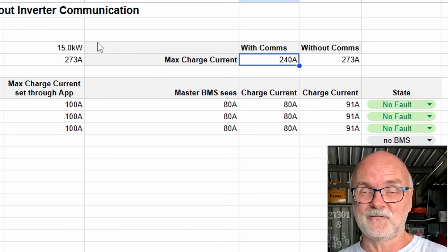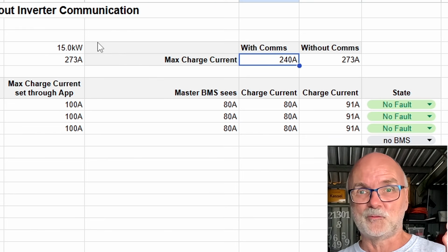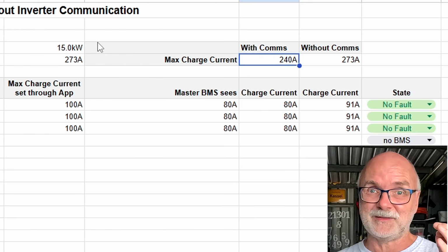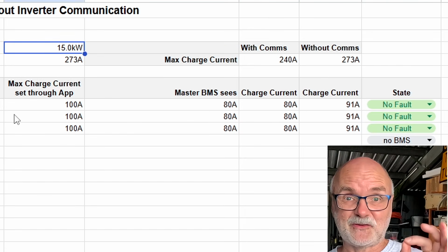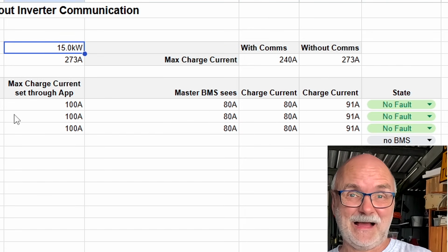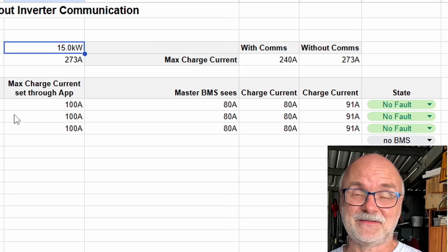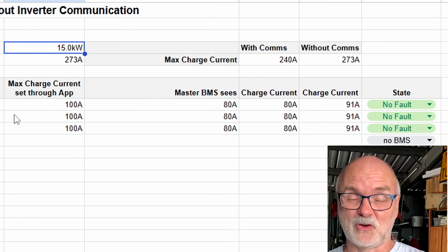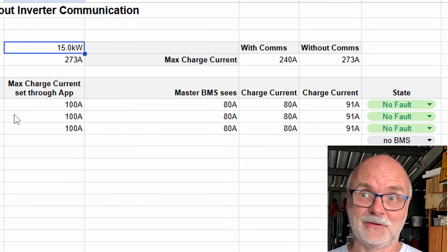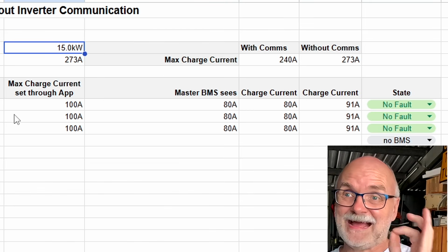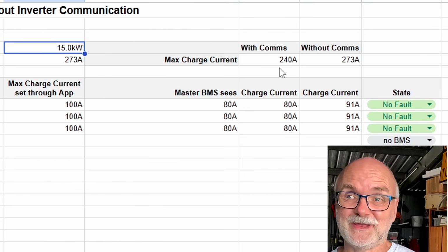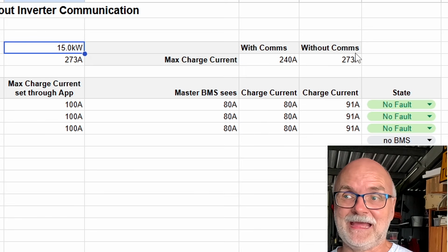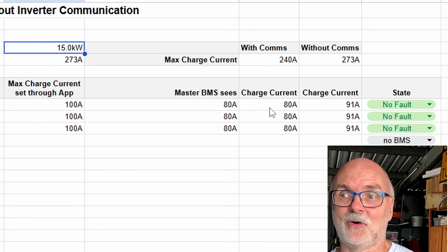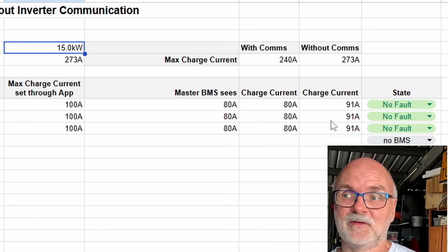They are over provisioning their solar system to what the inverter can handle, to what the BMS can take. And this gives you the very big advantage that even in cloudy weather, you still have a very decent charging speed into your battery. So you're over provisioning, oversizing your solar panels a little bit. So this is not an uncommon setup. So here with the communication, we are clipping our maximum charge current a little bit down from 270 amps to 240 amps only. So 80 amps into each of the batteries.